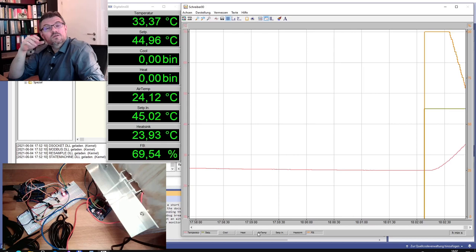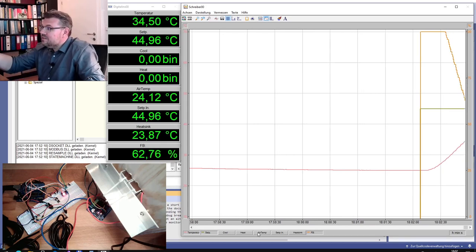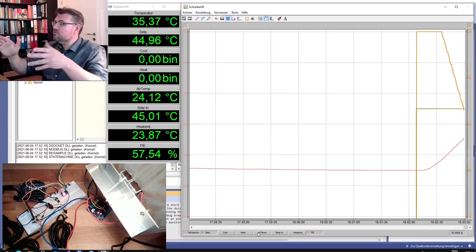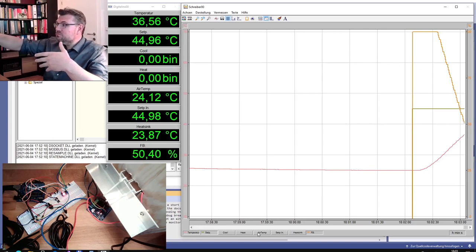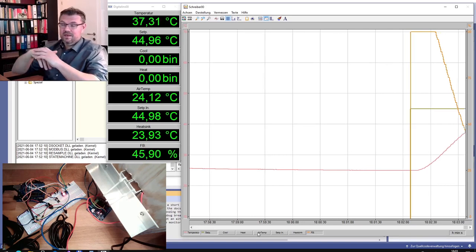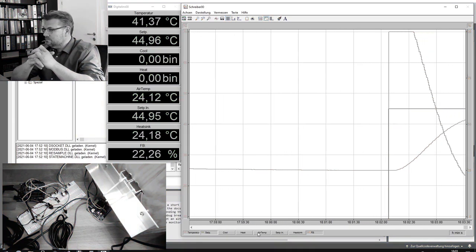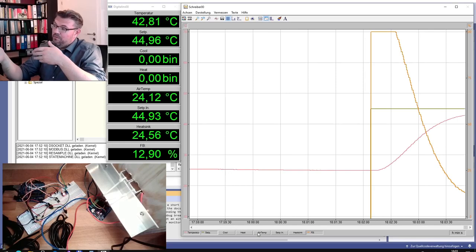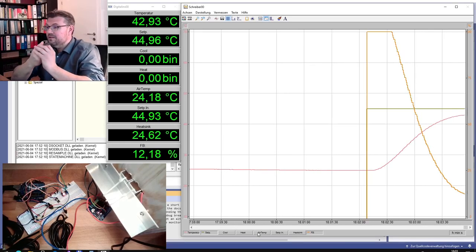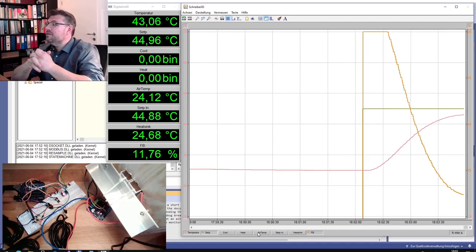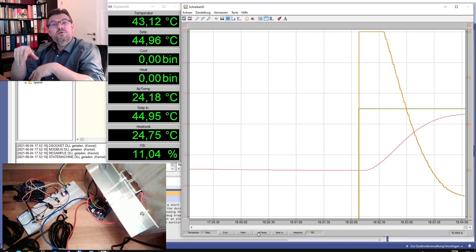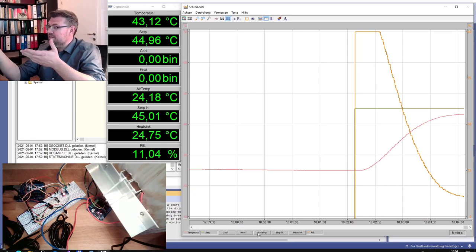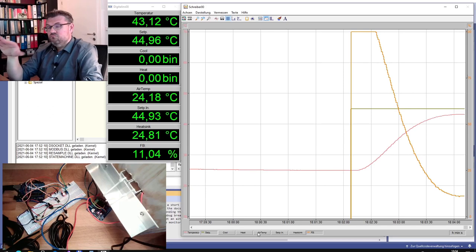We're dropping pretty fast. That's a typical behavior of a P-controller. If the proportional factor is high, it will also disappear pretty fast again. Before we had 15 percent heating, now we have 12 percent heating. So we will pretty much start to cool down. The only thing we have reached is a little bit more instability, a little bit more swinging it seems like. Let's wait a little bit. The reaction time was good. It really pushed at the beginning.